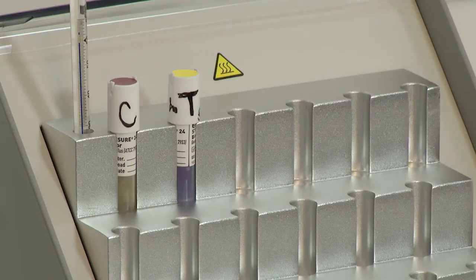To confirm sterilizing conditions were achieved during a cycle, compare the processed STERRAD CycleSure 24 vial with the positive control vial. The absence of a color change and turbidity in the processed vial indicates that the sterilization conditions were achieved. An example of this would be the media remaining purple as compared directly to a negative control.